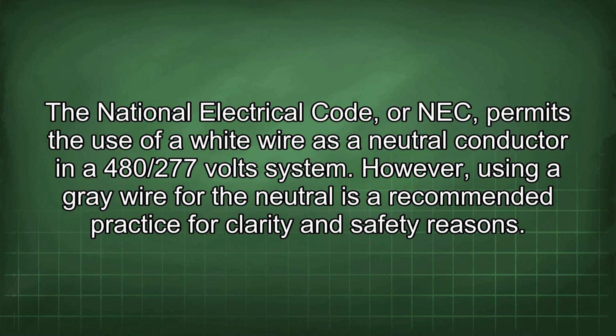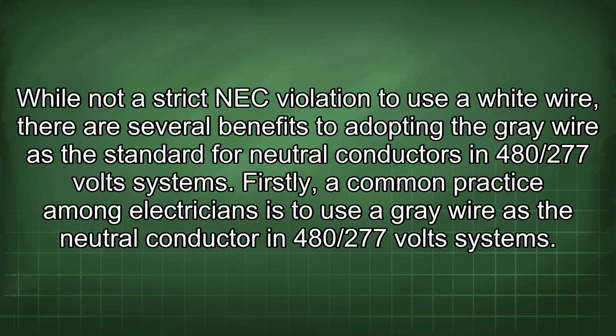The National Electrical Code, or NEC, permits the use of a white wire as a neutral conductor in a 480/277 volt system. However, using a grey wire for the neutral is a recommended practice for clarity and safety reasons. While not a strict NEC violation to use a white wire, there are several benefits to adopting the grey wire as the standard for neutral conductors in 480/277 volt systems.